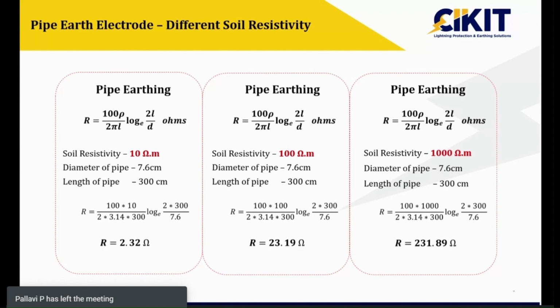From this, you can observe that we cannot provide a standard resistance value for a type of electrode. Some people will tell you that if you use this particular rod, you can achieve less than 5 ohms in all soil conditions. That is not at all possible. In earthing, the resistance value depends upon the soil resistivity only. If I install a rod which many people claim will achieve less than 5 ohms, in a soil resistivity of 1000 ohm meter the value will definitely be greater than 200 ohms. So don't believe those kinds of claims, because earthing mainly depends upon the soil resistivity. For that reason only, we have provided this particular slide.